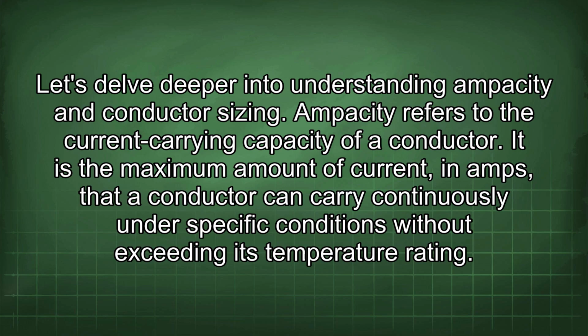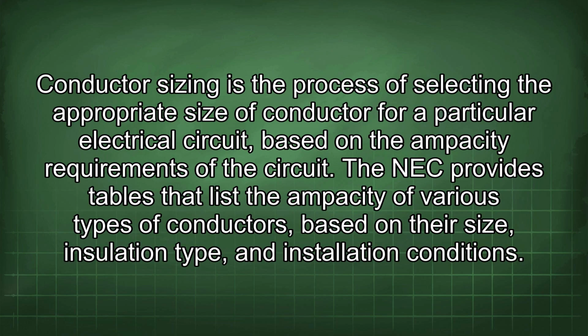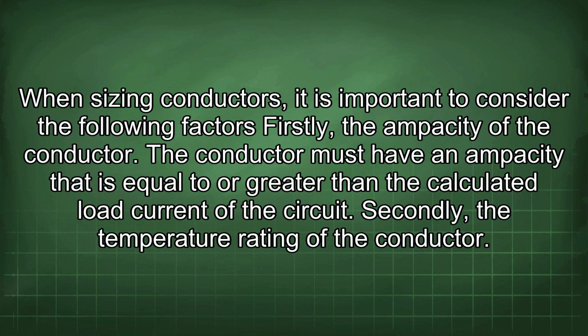Let's delve deeper into understanding ampacity and conductor sizing. Ampacity refers to the current carrying capacity of a conductor. It is the maximum amount of current, in amps, that a conductor can carry continuously under specific conditions without exceeding its temperature rating. Conductor sizing is the process of selecting the appropriate size of conductor for a particular electrical circuit based on the ampacity requirements of the circuit. The NEC provides tables that list the ampacity of various types of conductors based on their size, insulation type, and installation conditions. When sizing conductors, it is important to consider the following factors.